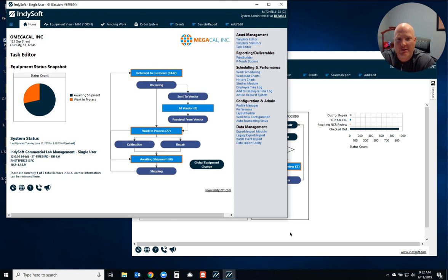There's actually a way in the system where you can directly create an export file of the certificates, the schedules, and the equipment that was calibrated or serviced, and then you can pass that file over to your manufacturer or your customer. They can then directly import it, saves them time from having to scan the certificate, update the schedule, or just manually run a calibration event. We'll actually take that from one system, export that, and push that directly over with this particular utility.